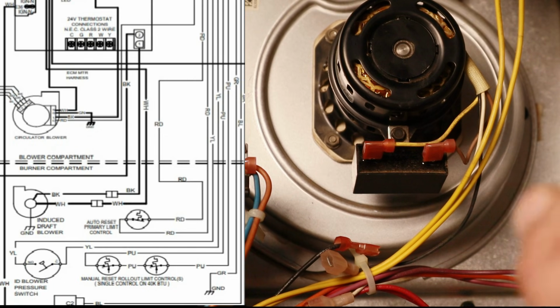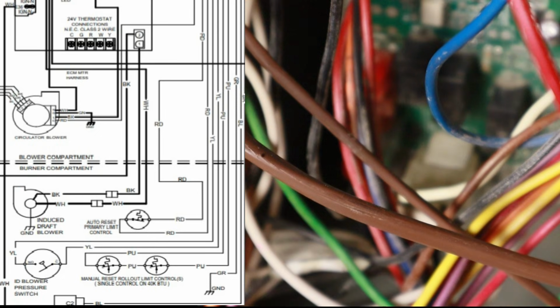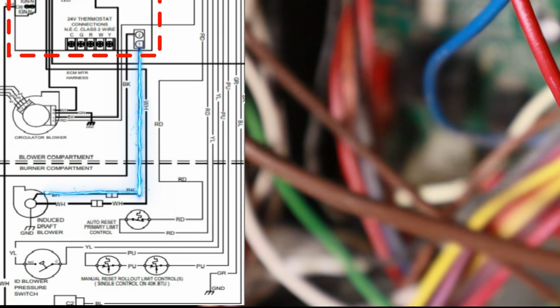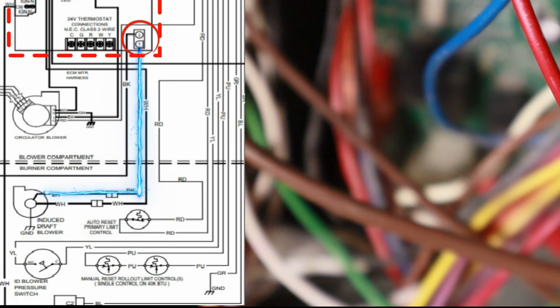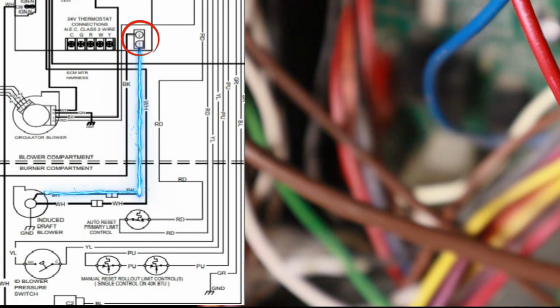So knowing that our inducer motor is the first thing to come on, when we look at our schematic, all we have to do is find the inducer motor and then look at the wiring in that schematic and see where it goes. So what the schematic is showing us is that black wire from that inducer motor is coming back to our control board to a little Molex plug. So that little plug down there in the corner, that is our power for our inducer motor off of the control module.